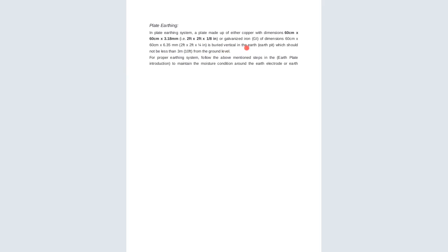It is buried vertically in the earth pit, which should not be less than 3 meters. We said the earth pit, or the hole that you are digging for the earthing, should go down at least 10 feet, or 3 meters to be precise. So for a proper earthing system, follow the above mentioned steps in the earthing plate introduction and maintain the moisture condition of the earth.